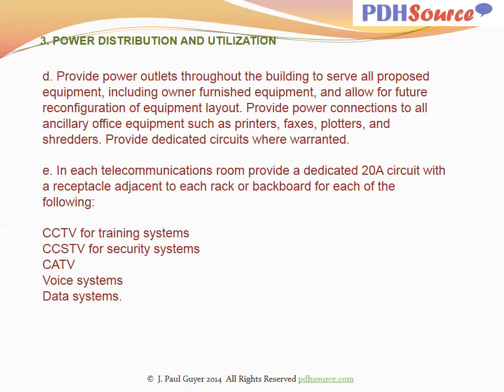Provide power outlets throughout the building to serve all proposed equipment, including furnished equipment, and allow for future reconfiguration of equipment layout. Provide power connections to all ancillary office equipment such as printers, faxes, plotters, and shredders. Provide dedicated circuits where warranted. In all telecommunications rooms, provide a dedicated 20 amp circuit with a receptacle adjacent to each rack or backboard for each of the following: CCTV for training systems, CCSTV for security systems, CATV voice systems, and data systems.